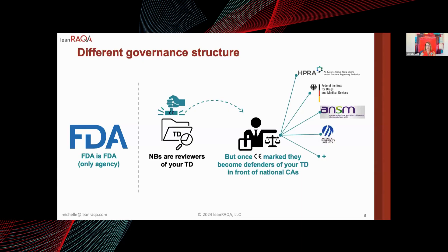Once a notified body provides a CE mark for your product, they become the defenders responsible for your technical documentation in front of national competent authorities — the in-country equivalent of the FDA. Each country in the European Union could have one or more competent authorities that these notified bodies must interface with. You can see how the number of agencies involved grows exponentially compared to the number and type of interactions you'd expect with the FDA.